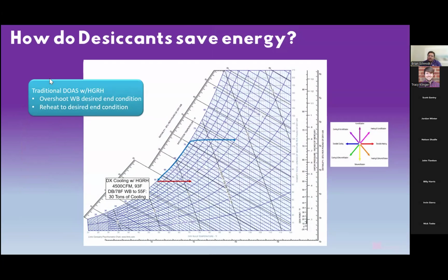So how do we do this, right? This sounds great. We're very efficient. We can do low dew points, but how do we do it? So obviously here's the psych chart, and what you're seeing here is the typical traditional DOAS with hot gas reheat, right? We have a starting point of outside air. We're going to cool down to the saturation curve. We're going to follow that curve all the way down to, let's just say, 55 degrees, and then we're going to use hot gas reheat to reheat it to space neutral condition. We're essentially overshooting the wet bulb desired end condition and then reheating to the desired end condition. So think of this as essentially overshooting your target and then having to reheat to get to your target, right? So it takes a lot of energy.